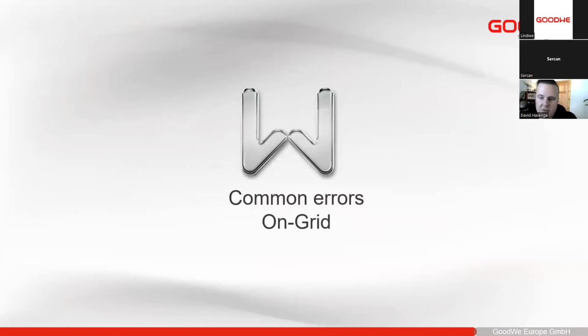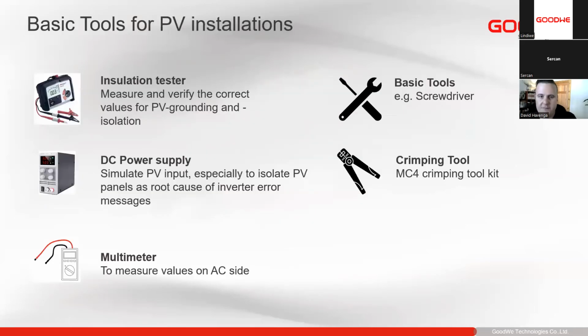So then we'll move to our on-grid inverters. The same basic tools are required here. As I mentioned, the DC power supply is a great tool to use here, especially if we are having any faults like insulation errors on the inverter, or if the inverter is not starting up or anything like that, we can use a DC power supply. Because most of the on-grid inverters only power up from DC, or if you need to do firmware updates at strange times, it's always good to have a DC power supply handy.